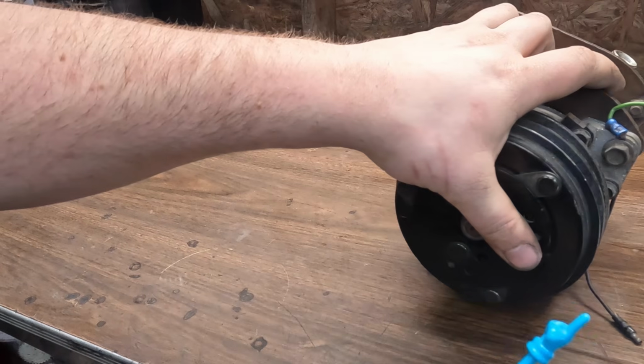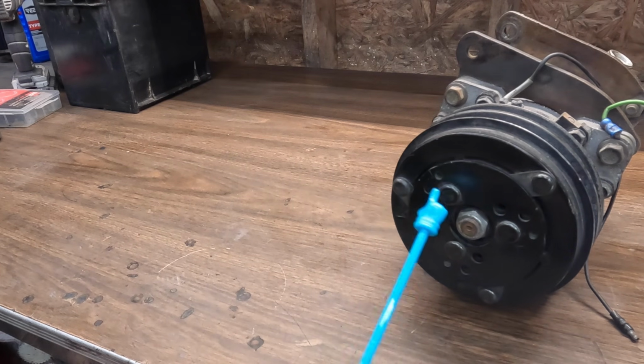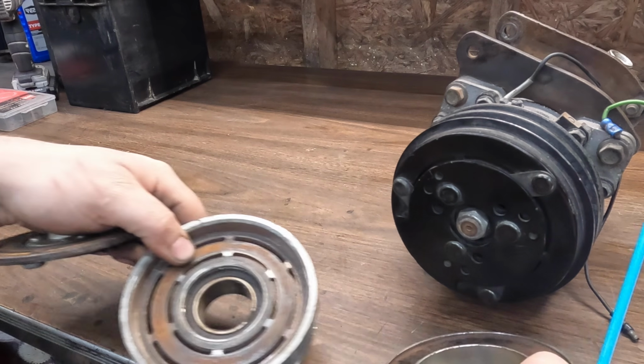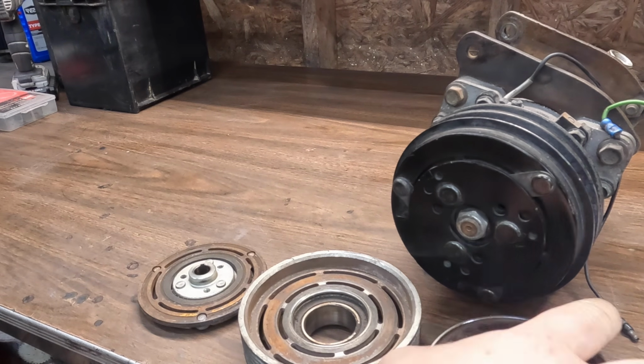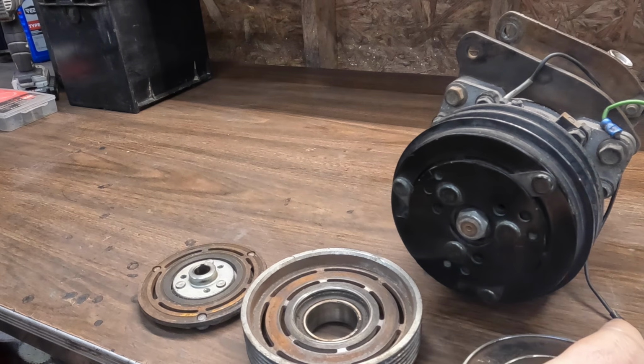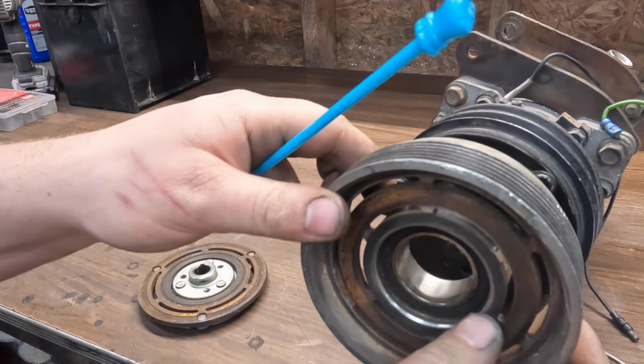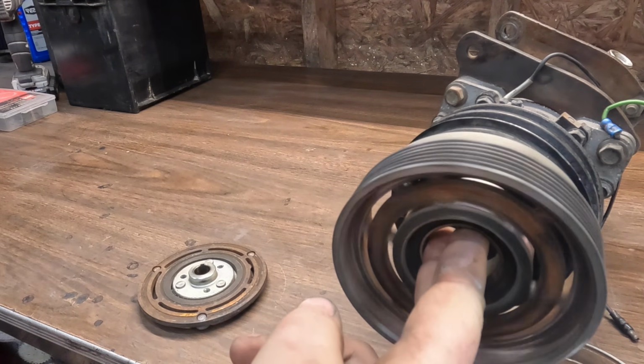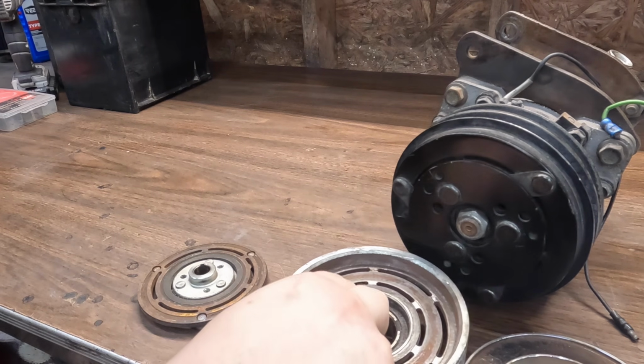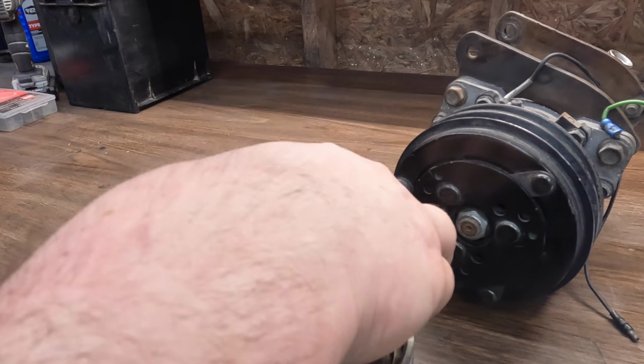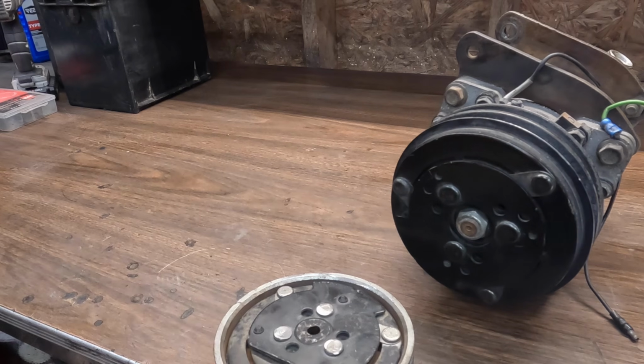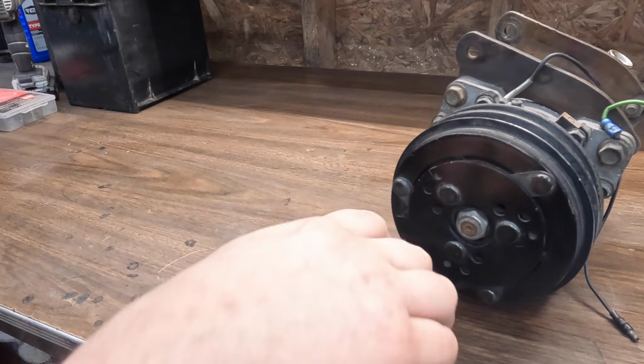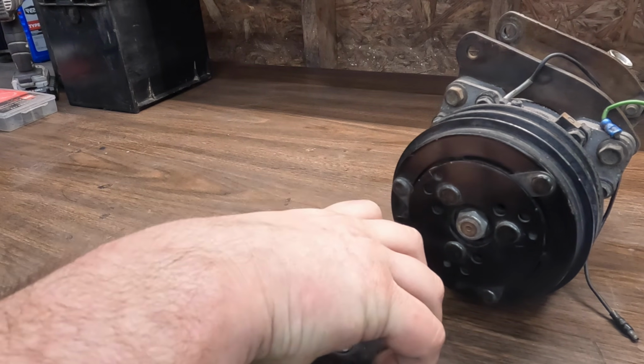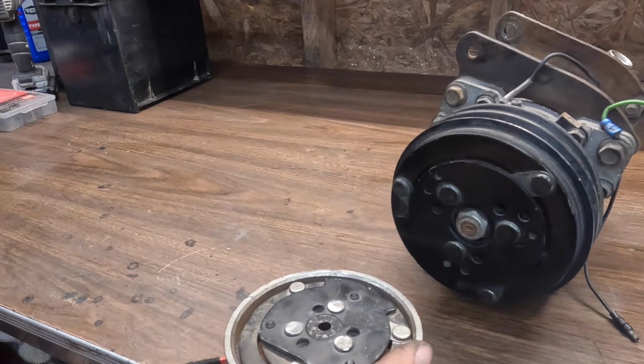Starting at the front, we see the pressure disc and spring apparatus of the clutch. Were I to take that apart, this is what we'd find: on the front of the compressor there's a big electromagnet, and then this, the idler pulley. There's a big bearing in there so your belts can ride on it even when it's not driven. So that goes like that, and that plate goes on the front and connects to the shaft. You put power to the electromagnet and it sucks that down into the plate and makes the compressor spin.